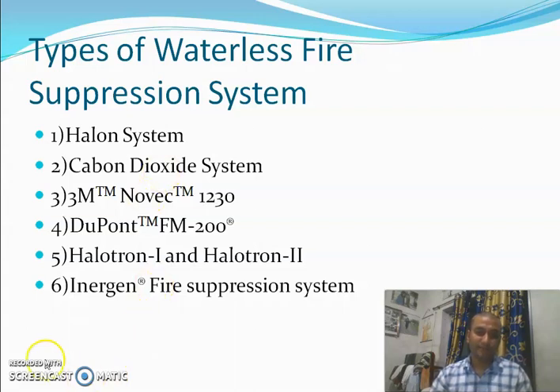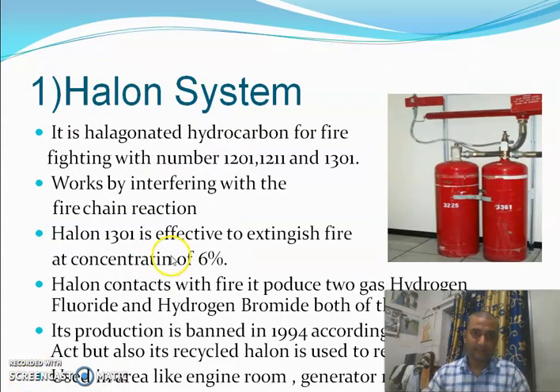Now moving towards the first: Halon system. Halon is the halogenated hydrocarbon used for firefighting, with numbers 1201, 1211 and 1301. It works by interfering with the fire chain reaction. Halon 1301 is effective to extinguish fire at a concentration of 6%. Halon reacts with fire to produce two gases, hydrogen fluoride and hydrogen bromide, both of which are toxic and harmful.